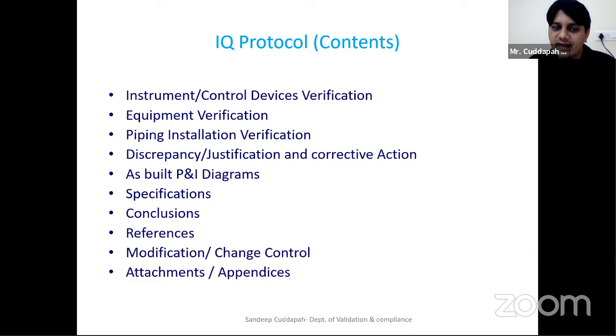Then different instruments, equipment, and pipings. For the pipings, in installation qualification you will have a drawing called the P&ID. This is the piping and instrumentation drawing. It gives you which pipeline or which line is connected to which end, and from where to where the flow happens. All these things are defined in the piping and instrumentation drawings. Then you have to give the specifications of your equipment. Finally, you conclude whether you are meeting all the specifications or not.